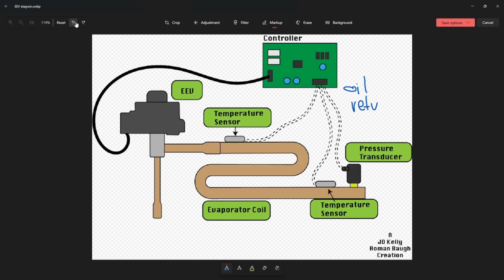Most of the time, that is on your top of the line equipment, like your Carrier Infinities, your Trane Platinums, your Rheem EcoNets. They all use pressure transducers because they have those dedicated modes to help protect the coil from freezing up and to help protect the compressor from losing all of its oil.